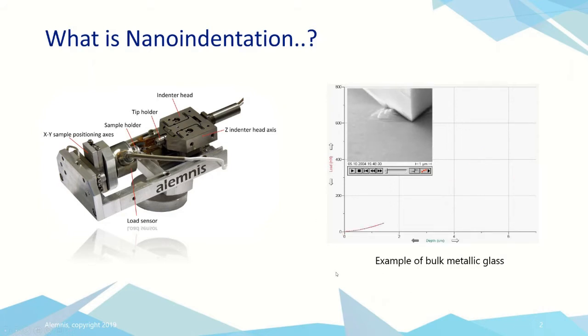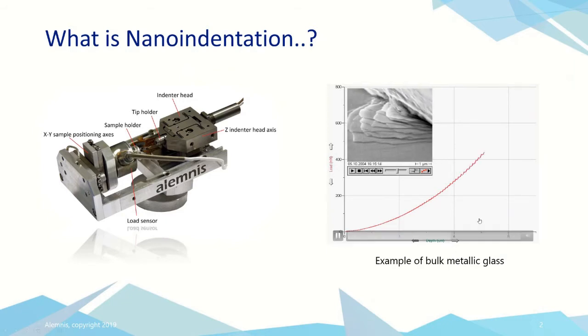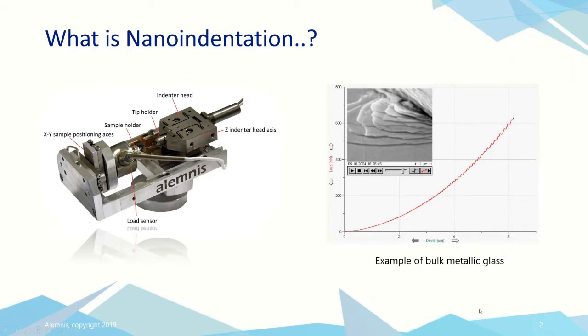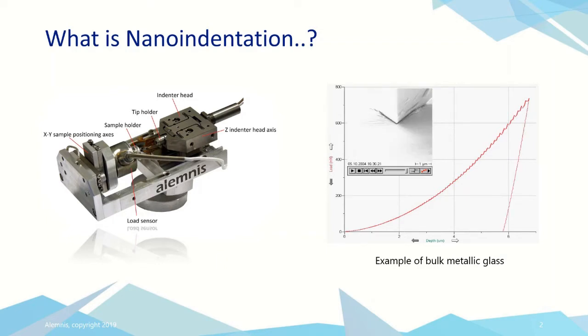And if we do that in the SEM, we can also see in situ what's going on. So, for example, in this case, we see a load depth curve, but it doesn't tell us what's happening at the material surface and what is the response of the material. As you can see here, there are little striations on the loading curve, and it's only with in situ viewing that we see that we've got slip happening in the material. So the combination of SEM with nanoindentation is already very advantageous. And then when we bring AFM into the mix, we can learn a lot more about the sample surface itself.